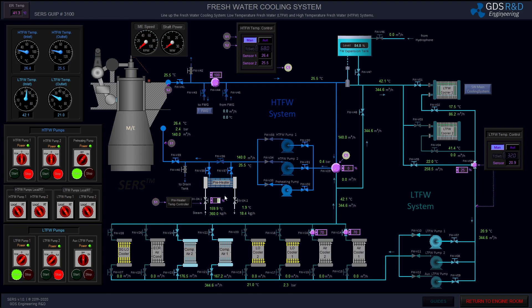The preheater temperature controller is in manual mode, so I will be able to open the valve manually. I'm now opening 20% on the steam line. I will adjust the steam flow rate to about 180 kilograms per hour.